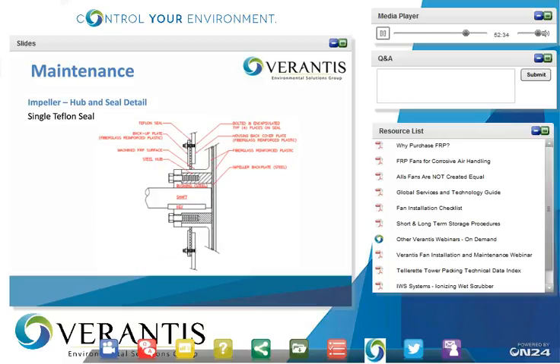Maintenance: impeller, hub, and shaft seal. This basically just shows the Teflon seal mounted on one of our fans. Starting at the left-hand side top, that's the Teflon seal, Teflon membrane. There's a backup plate on the very outside that's made of FRP. There's a machined FRP surface on the impeller hub that extends through the back cover, or the back of the fan housing, and the attachment is outside of the airstream. You can see the steel hub that's encapsulated with the FRP.